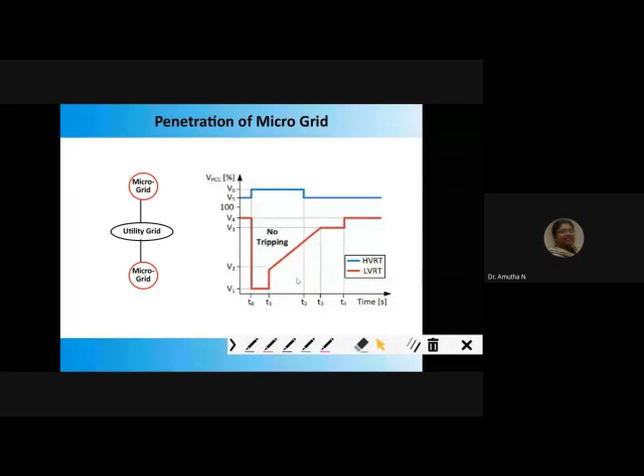During the fault conditions, the voltage will be low. But because of the low voltage, the microgrid or the distributed generators which are supplying should not be removed. They have to continue to operate at least for the few seconds given by the grid, for example from T0 to T1. From T0 to T1, it should not trip, that is, it should not be disconnected. It has to completely supply the load.